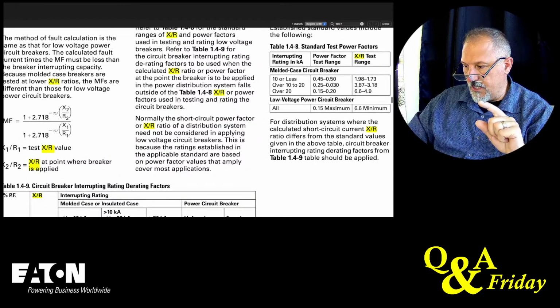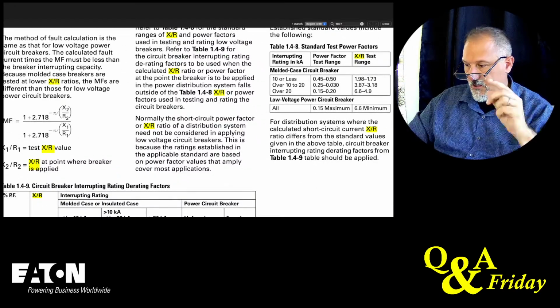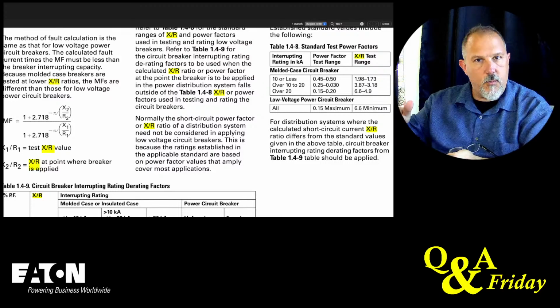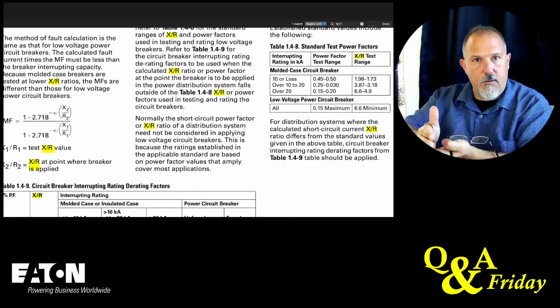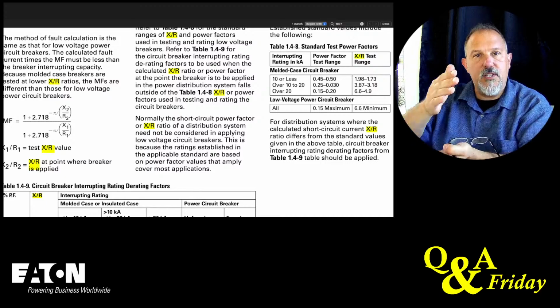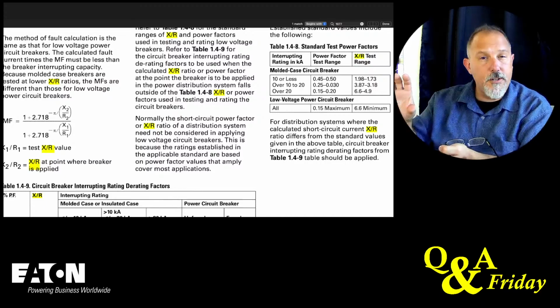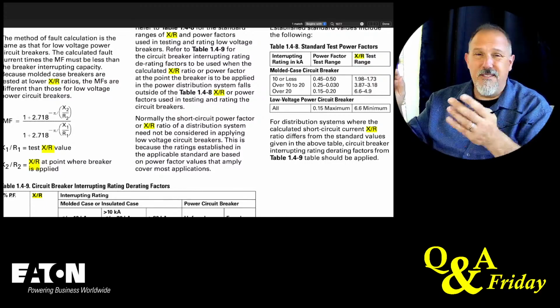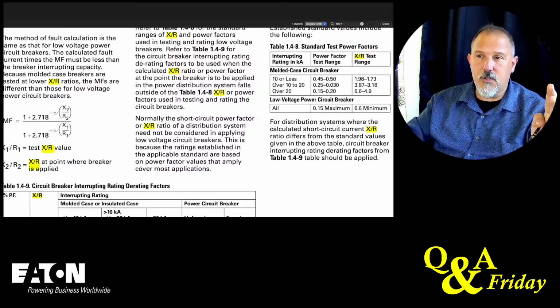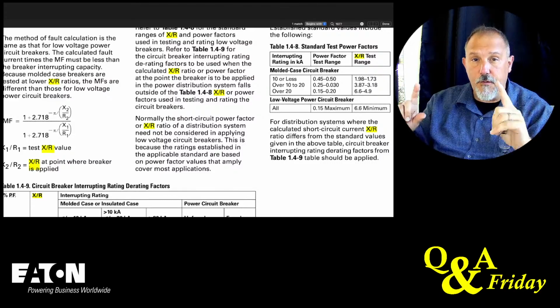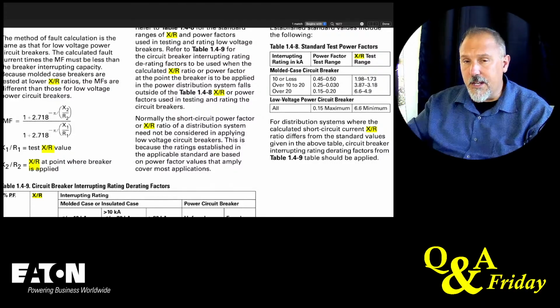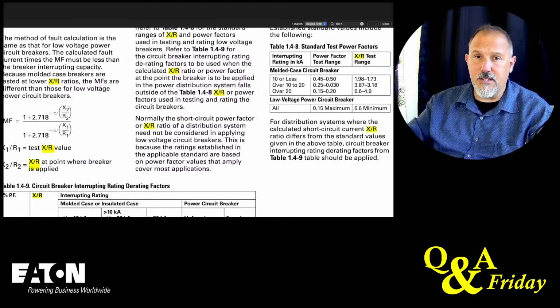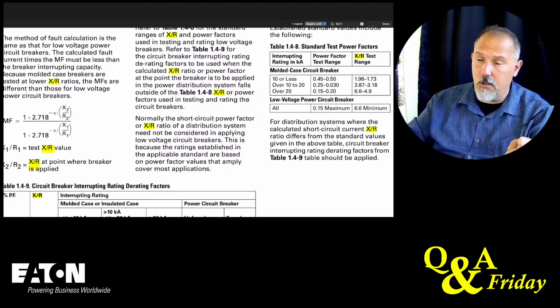Look at this. Molded case circuit breaker standard test power factors. So what we do is we create a circuit. When we have a circuit breaker interrupt the current, we set a worst case power factor. Not necessarily the worst, but it's probably the worst case that you'll find. Can you find X to R ratios that exceed these values? Yes, but it's very difficult. It's not very common, but it is something you need to look at.